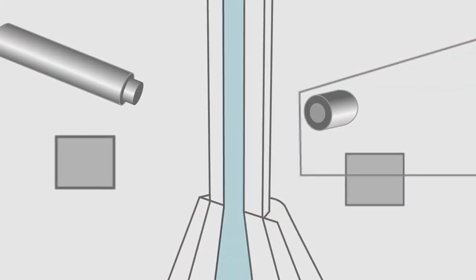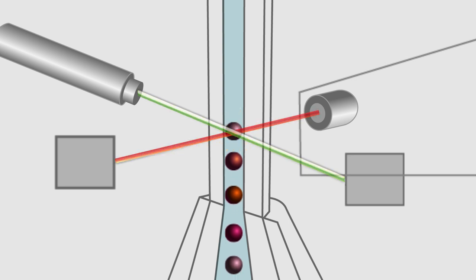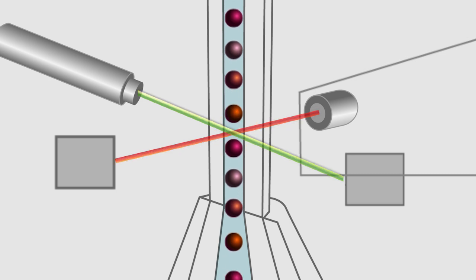XMAP Technology uses two primary methods for detection, flow cytometry and CCD imaging. In flow cytometry, beads are passed through a flow cell where one laser is used to excite the fluorescent dyes for bead identification, and another laser is used to excite and quantify the assay reporter dye.